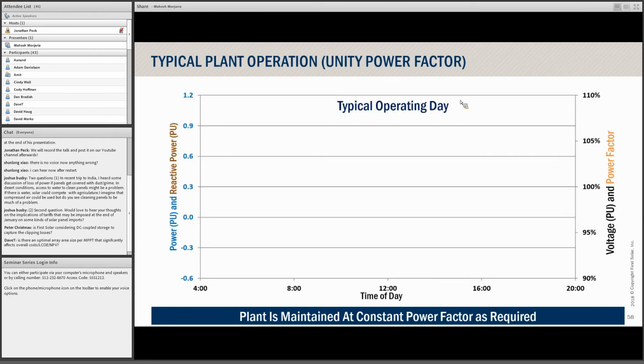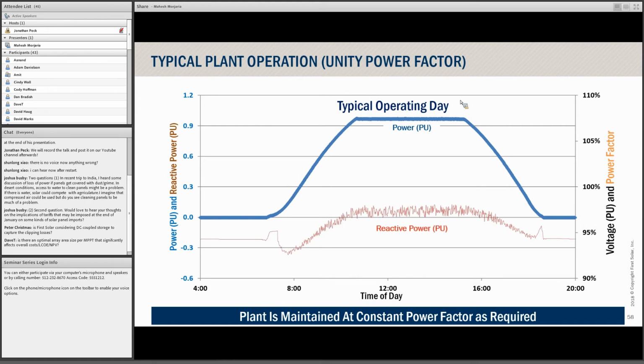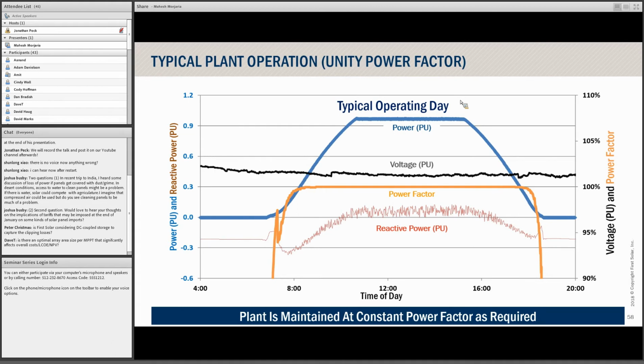So this is typically how the plant operates, where the power of the plant comes down. This is a nice clean day, and you can see the power going up in the middle of the day, and then it is limited because there's a transmission constraint or the plant level constraint, and we maintain that. There is some reactive power produced in the plant, which we manage in order to get a constant power factor. See the power factor line is at 1.0 and it remains constant. And the voltage is maintained pretty much by the nuclear power station, so we don't maintain the voltage. So this is how the plant runs quite well, as you can see.